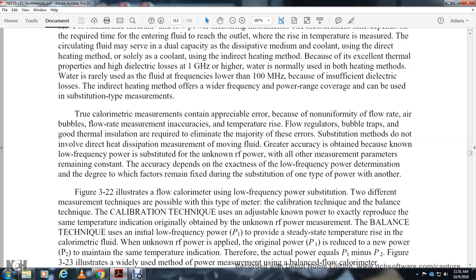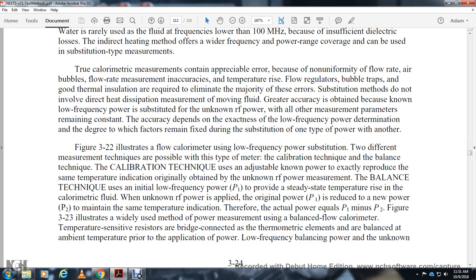The substitution method does not involve the direct heat dissipation measurement of the moving liquid. Greater accuracy is obtained because the known low frequency power is substituted for the unknown radio frequency power with all the measurement parameters remaining constant. The accuracy depends on the exactness of the flow rate and the power determination, and the degree to which the factors remain fixed during the substitution of one type of power with another. Figure 322 illustrates the flow calorimeter with low frequency power substitution. Two different measurement techniques are possible: the calibration technique and the balance technique.